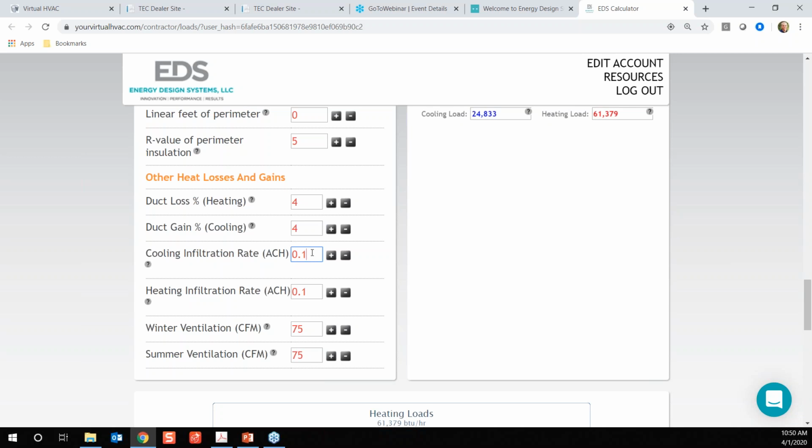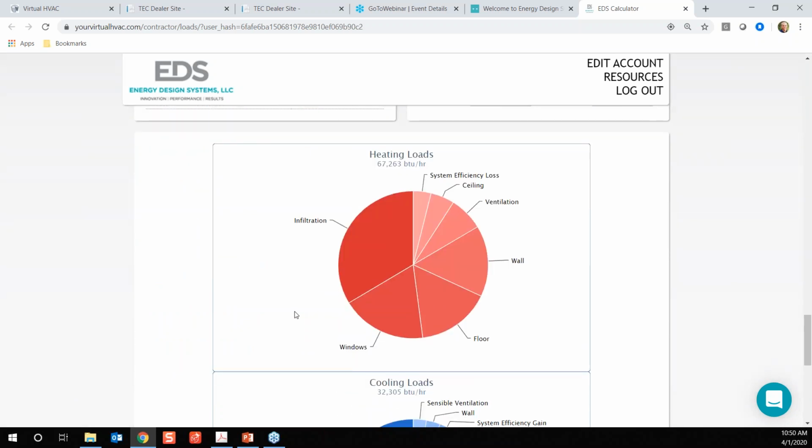So let's just say it's 96. That is 7 degrees above my design temp for outdoors. And that thing still did not need stage 5. It needed stage 5 coming out of setback. But once I got up to temperature or down to temperature, it didn't need the 5th stage. So I still had extra capacity in that 3-ton. So I could probably go with lower numbers in those cases. The other thing it's going to do for you, actually, let's see if we have any questions here.